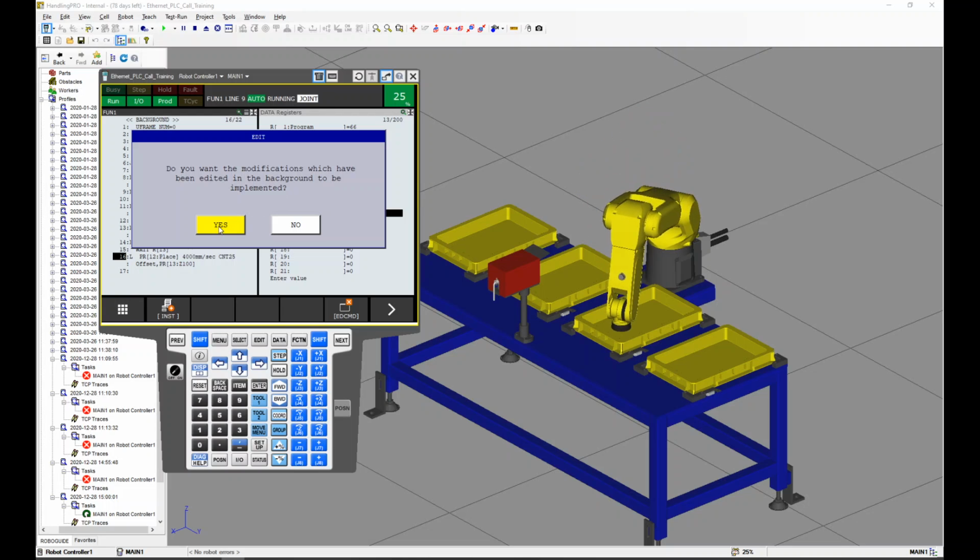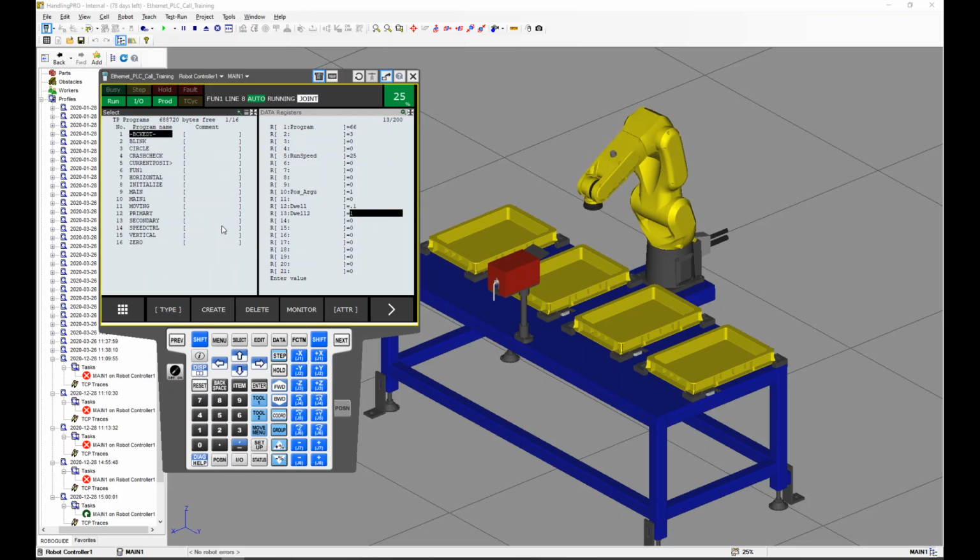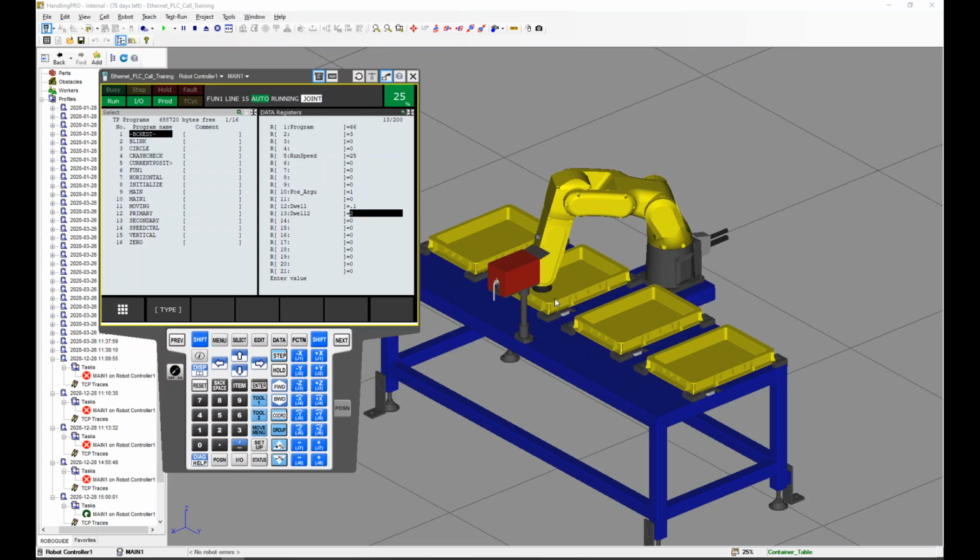When I click yes, it is important that I click yes while this robot is not actively running that piece of the program. So the robot's still running production, but I'm gonna click it when it is at the home position, main loop. So here we go, robot's home, I click yes. Now, those edits have already happened. You see the robot already behaving. At the pick, it's a short delay, and at the place, it's a long delay. We can exaggerate that. Quick pick, long place. So now we've made that online edit while the robot was running.